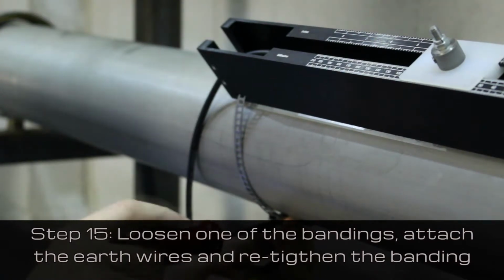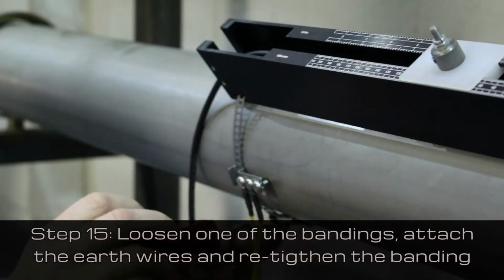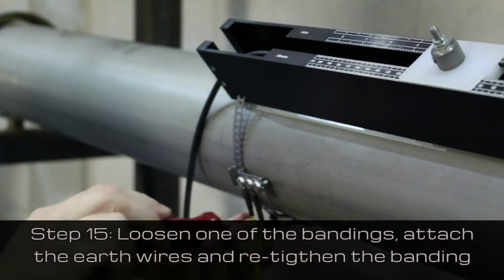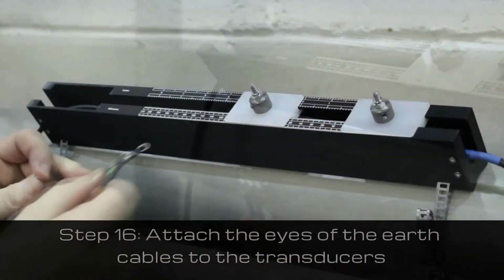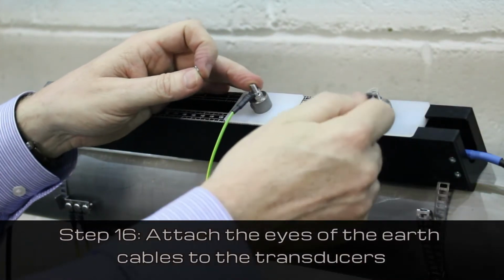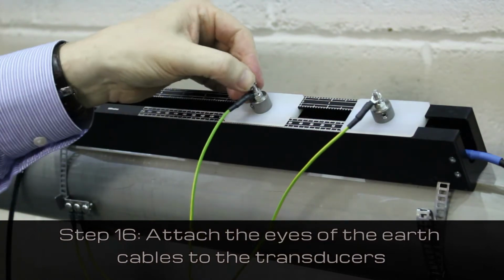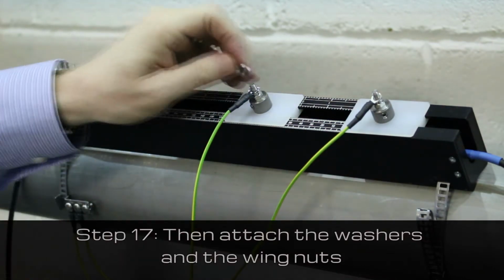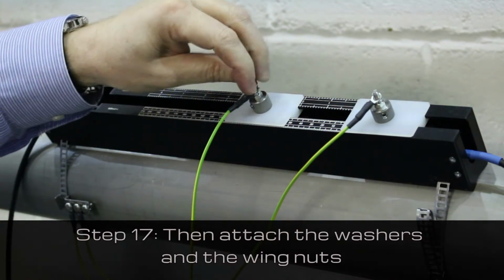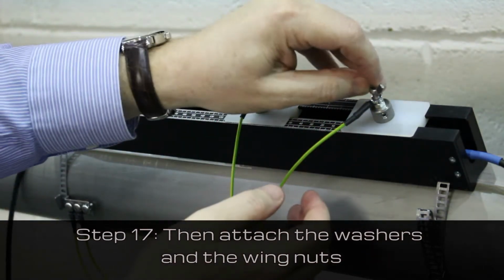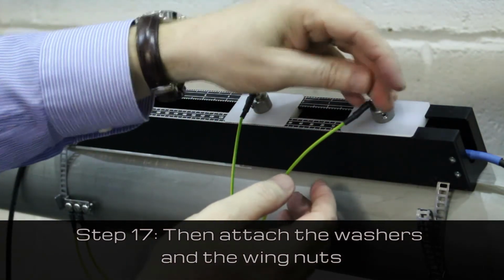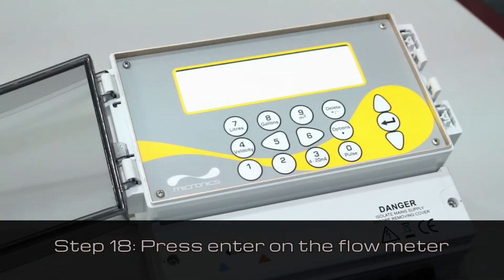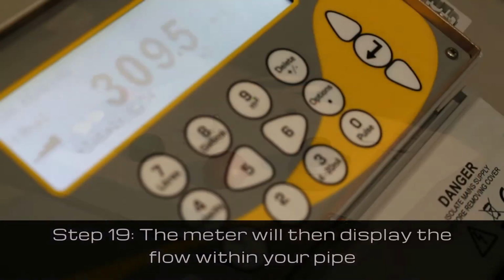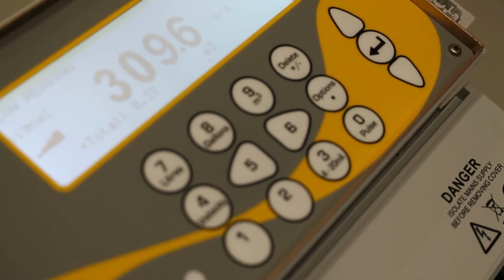Loosen one of the bandings, attach the earth wires and re-tighten the banding. Attach the eyes of the earth cables to the transducers, followed by the washers and the wing nuts. Press Enter on the flow meter. Once the flow has been switched on, the meter will display the flow within your pipe.